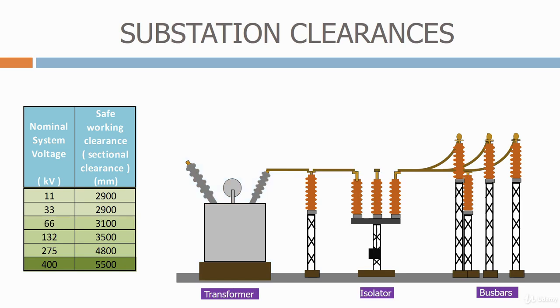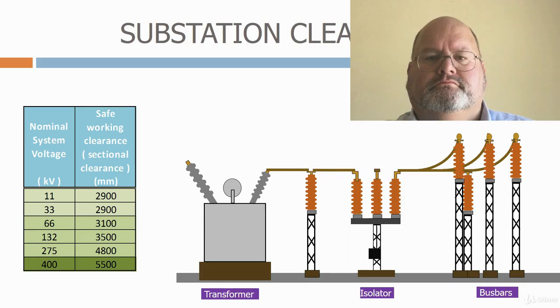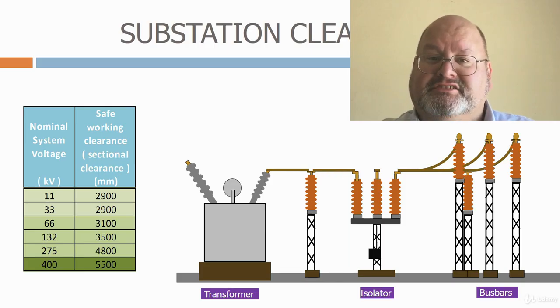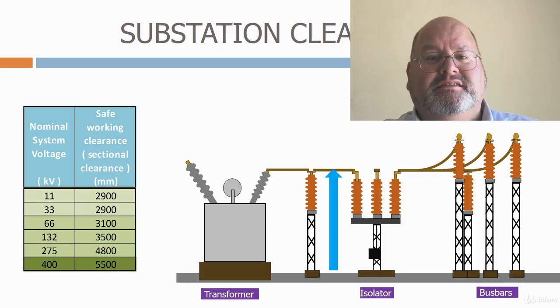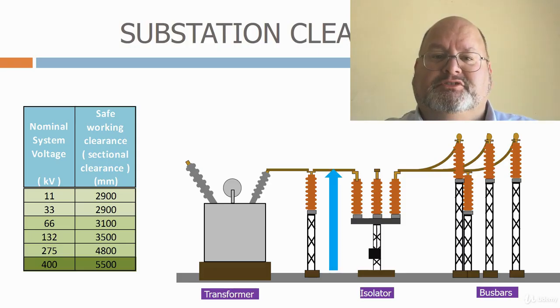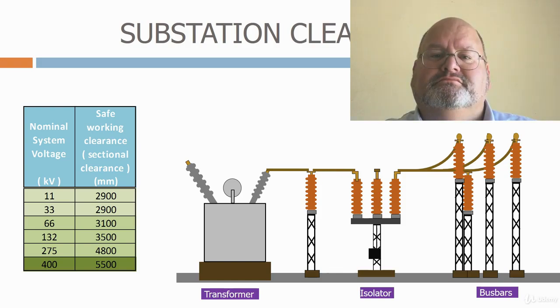The sectional clearance also defines the height of the bus bar from the ground. The higher the voltage, the higher the bus bar needs to be. This clearance distance includes for any objects or foundations the personnel can stand on inside the substation. The phase-to-earth and phase-to-phase clearances are fixed distances and define the equipment dimensions and spacing between the bus bars, and we can't do much to change them in an air-insulated substation. The sectional clearances depend on the operation of the substation, which gives us some options.